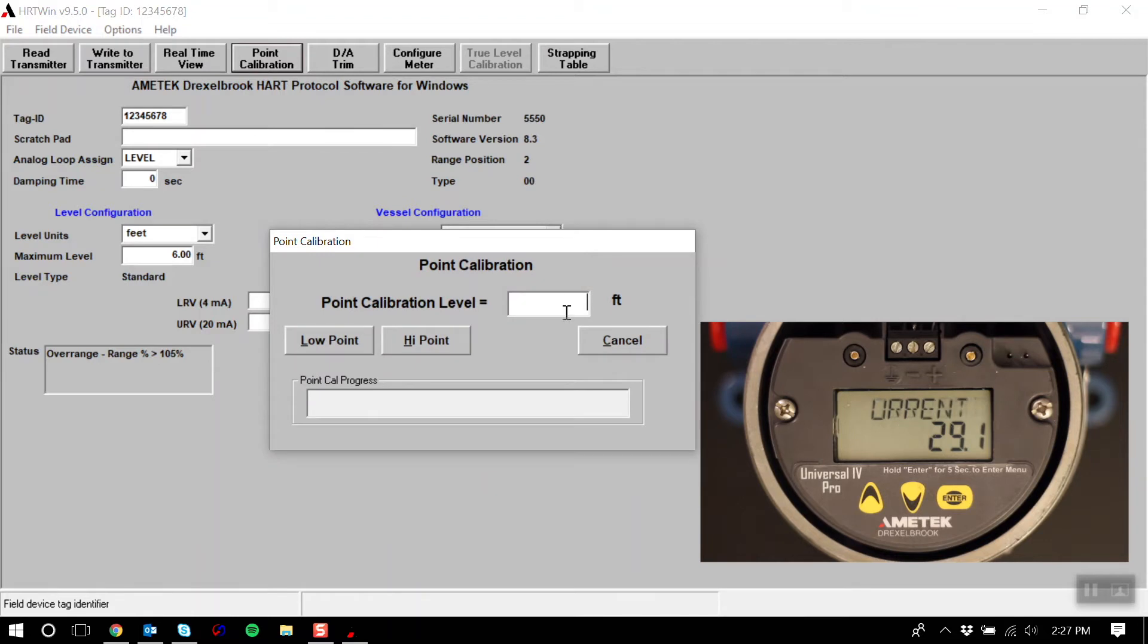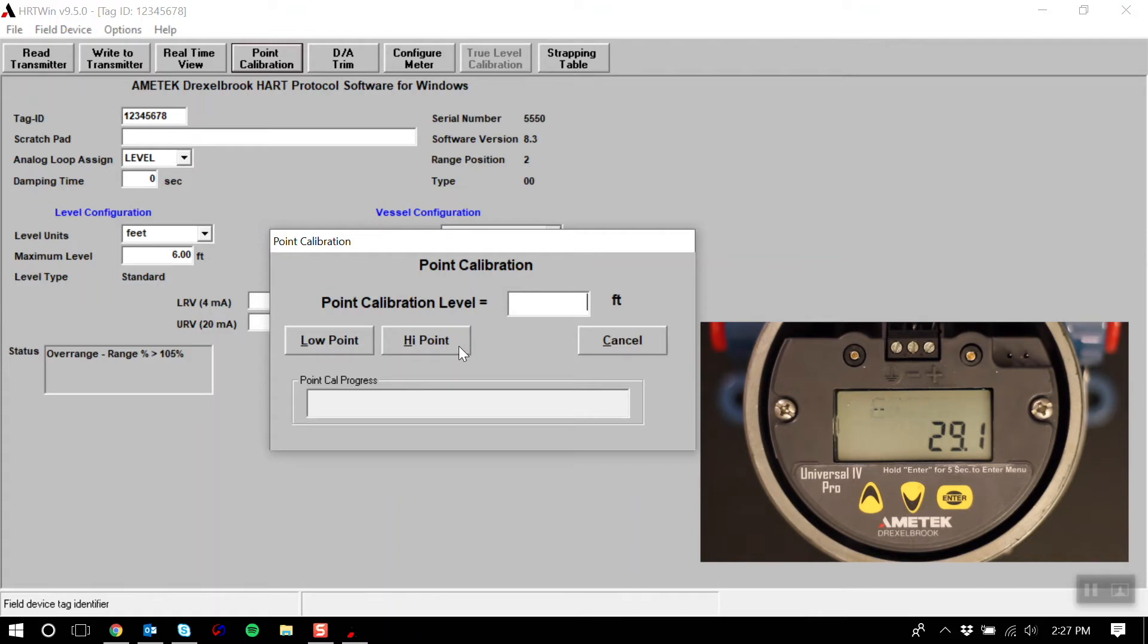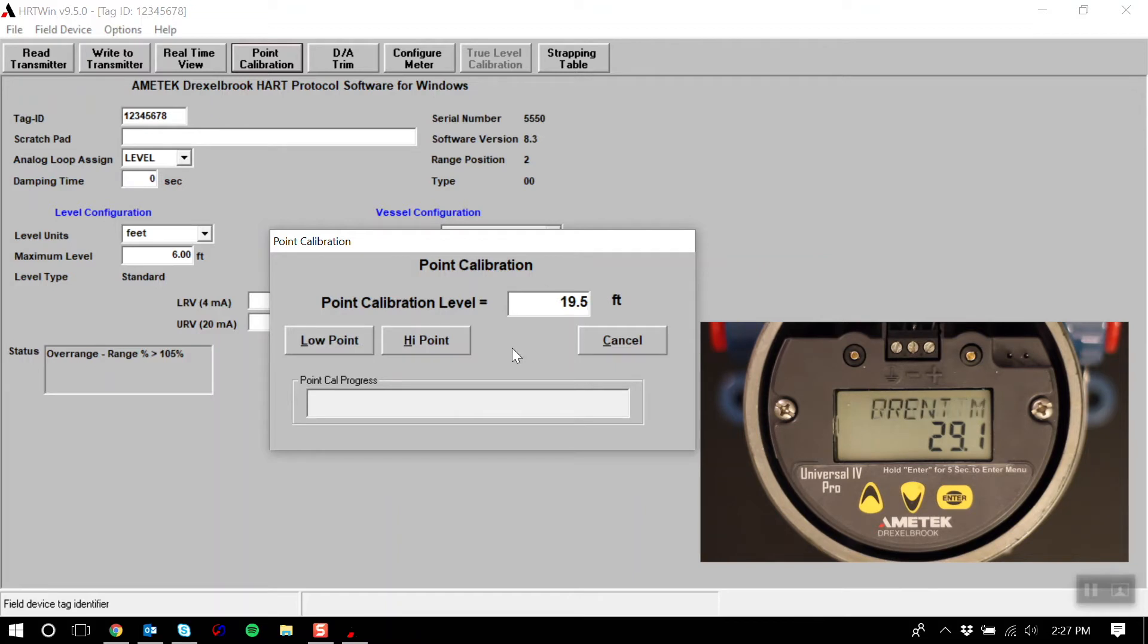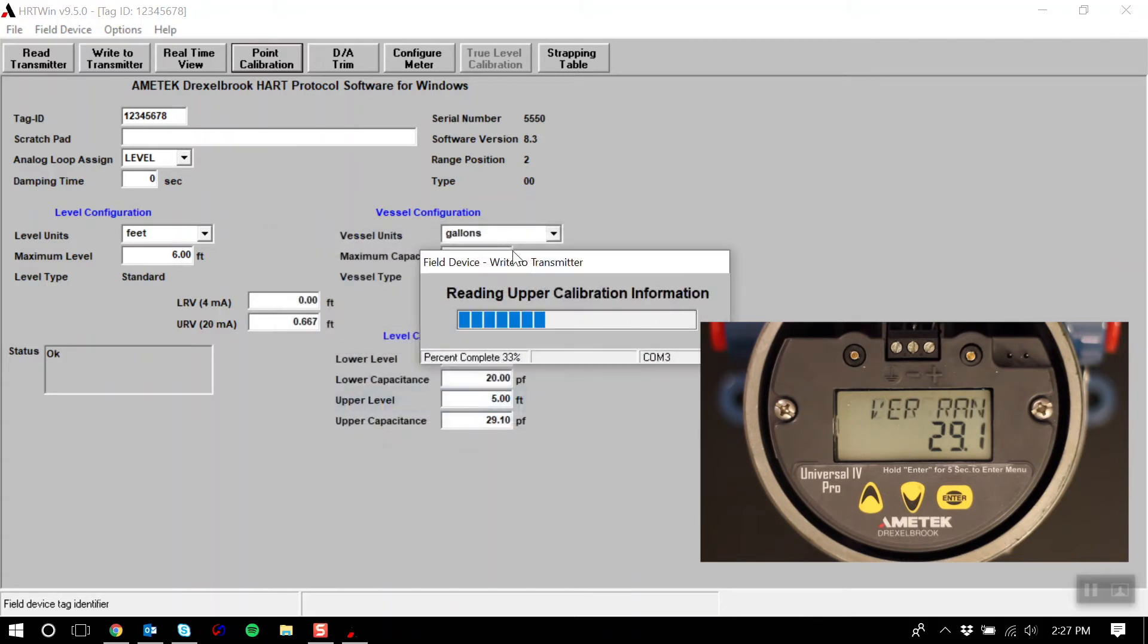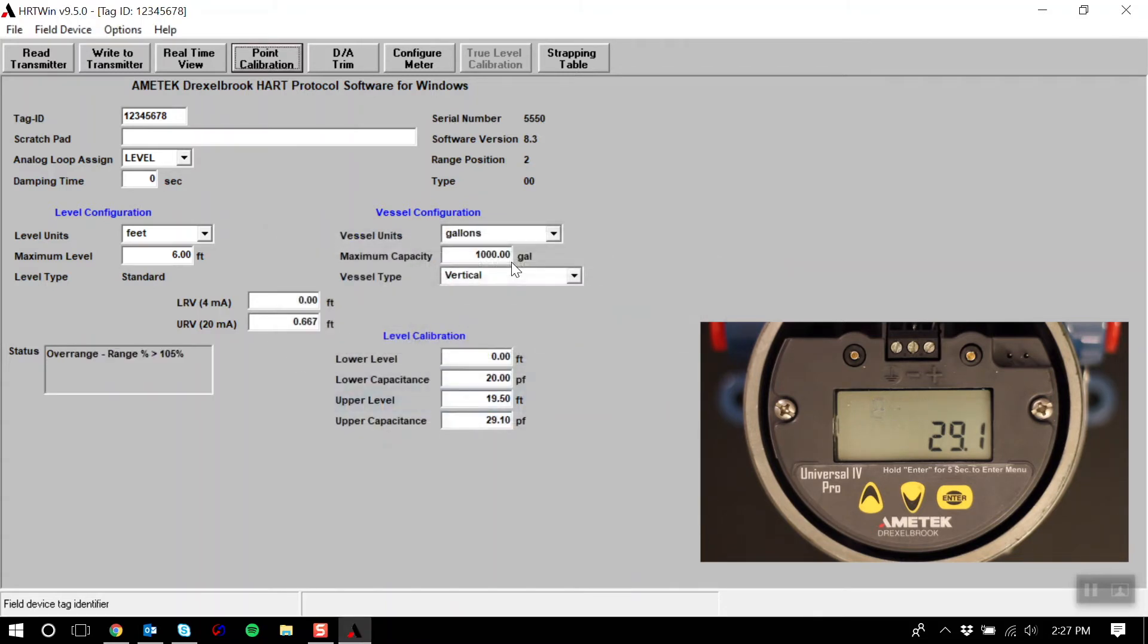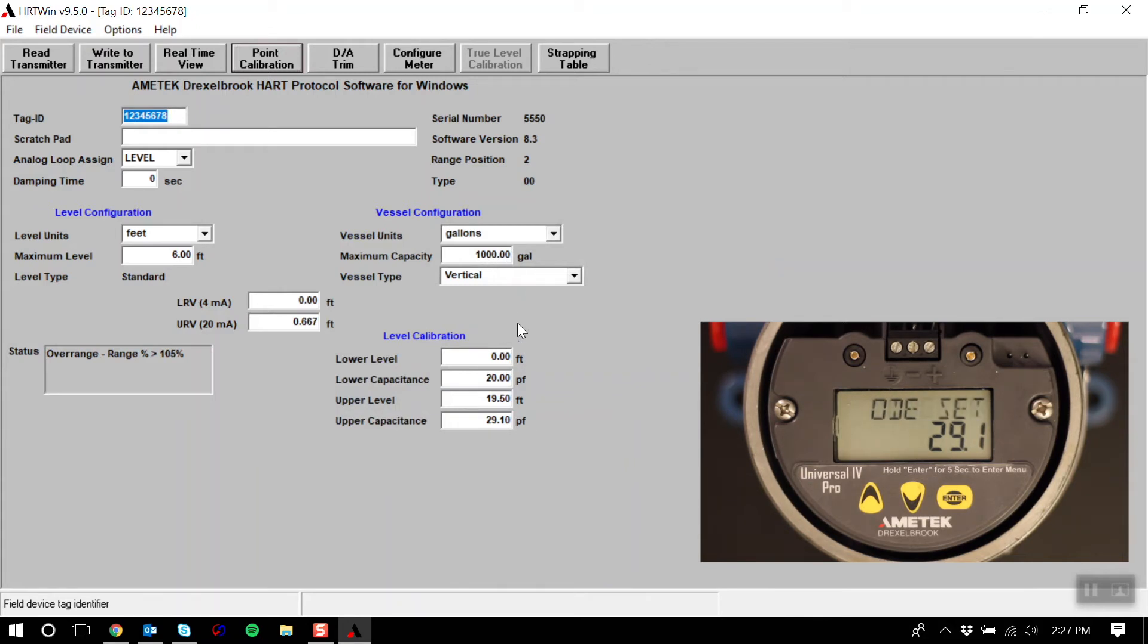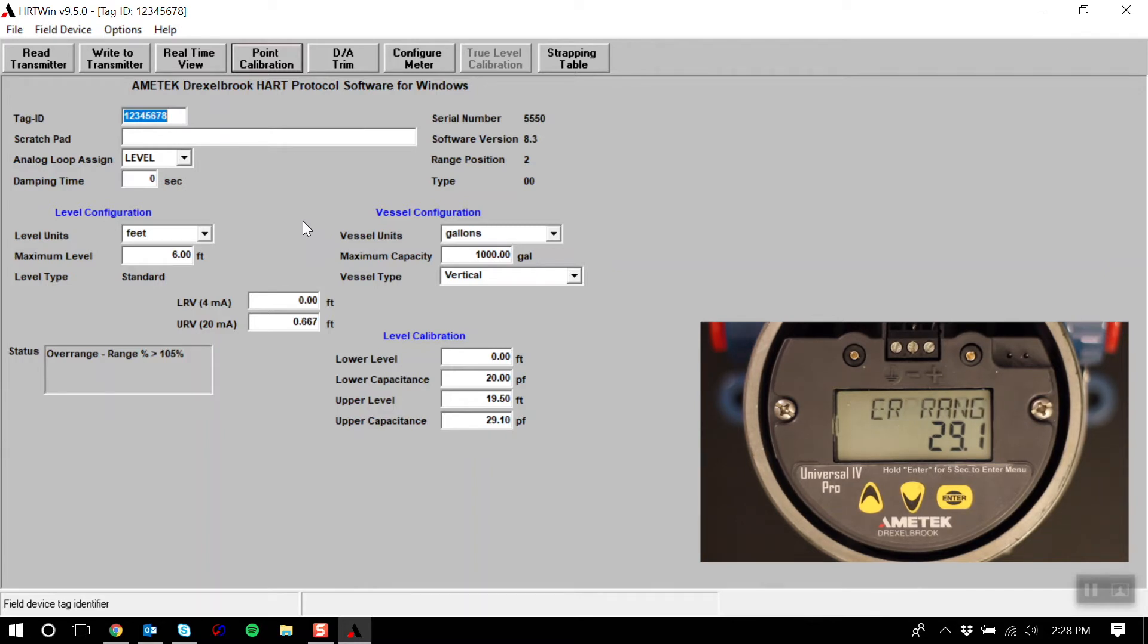Here you will enter your known level value, and then designate whether this point will be your high or your low point on your linear line. For example, if I enter 19.5 feet and make this my high point, it will write to the transmitter that 19.5 feet is my high point. Now the next point needs to be lower, hence my low point. This doesn't need to be done right away. The next time the level drops to a known value, I can repeat this process for the low point.